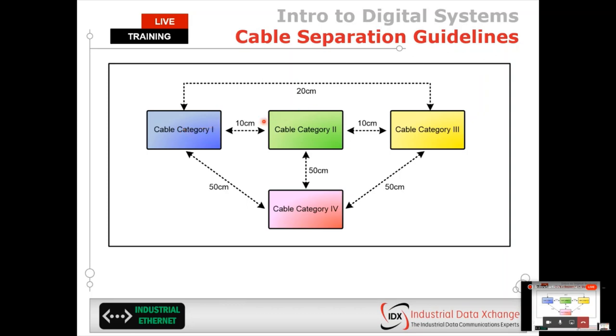Cable category two is anything above 60 volts DC, 25 volts AC, up to 400 volts AC and DC. This needs to be separated by at least 10 centimeters from cable category one. So if you have a 220 volt supply to one of your power supplies in a cabinet, this needs to be at least 10 centimeters away from your industrial Ethernet cable at all times.